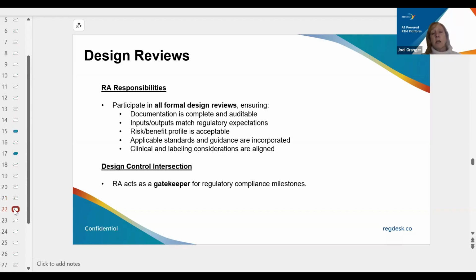Your design reviews are going to happen at different phases in the process, and regulatory is a required participant for those formal design reviews. During those meetings, you should be reviewing from a regulatory perspective that the documentation is complete and auditable for that phase. Normally, each phase will have a list of deliverables that are required, and you need to make sure that each of those deliverables are met.